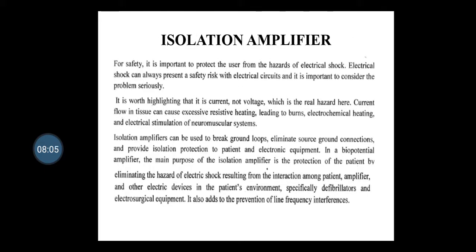For safety, it is important to protect the user from the hazards of electrical shock. Electrical shock can always present a safety risk with electrical circuits, and it is important to consider the problem seriously. It is worth highlighting that it is current, not voltage, which is the real hazard here. Current flow in tissue can cause excessive resistive heating, which leads to burns, electrochemical heating and electrical stimulation of the neuromuscular system.